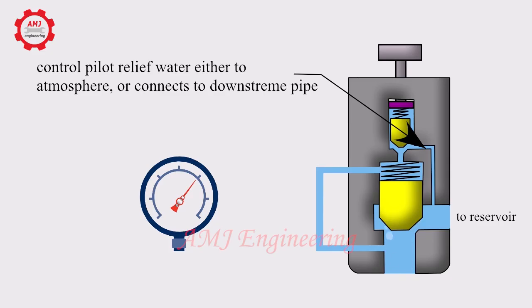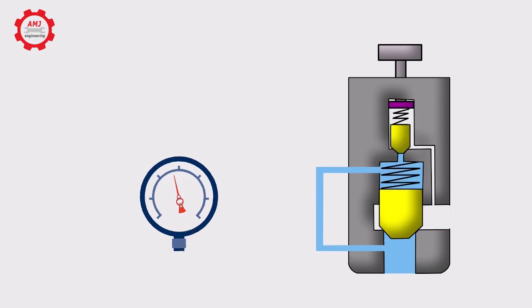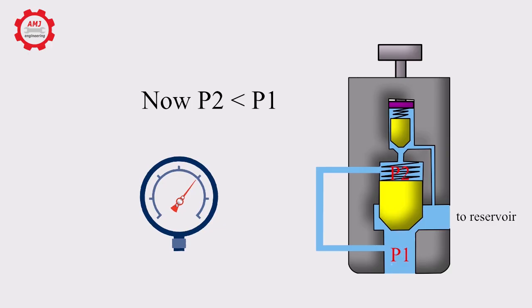The control pilot opens either to the main valve exhaust pipe or to atmosphere. The pilot is designed to open gradually so that less of the system fluid is lost during each relief event. The piston lifts in proportion to the overpressure. Blowdown is typically short.